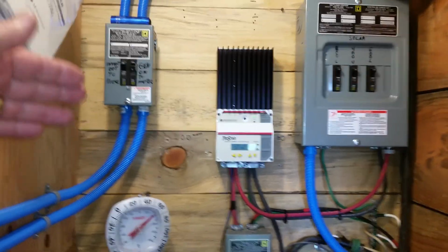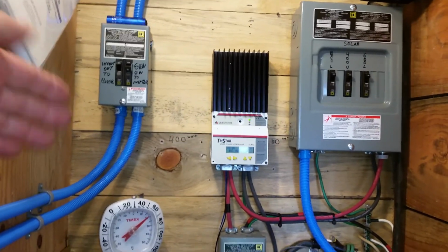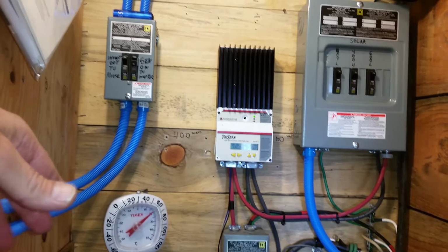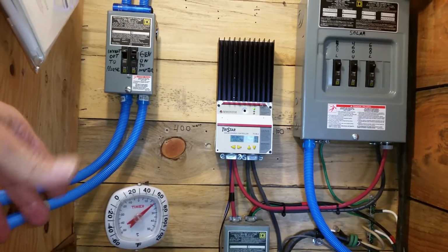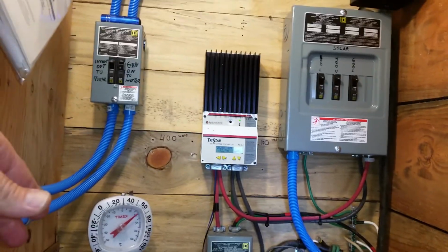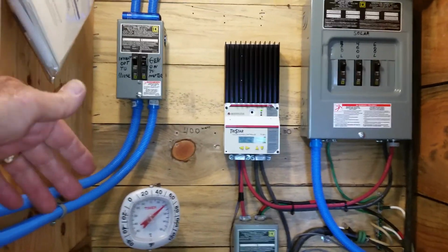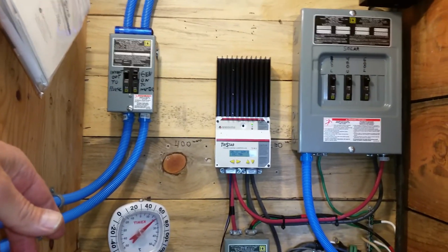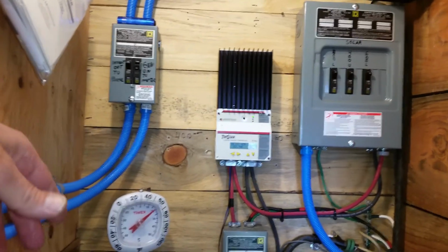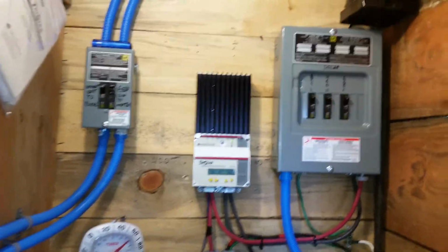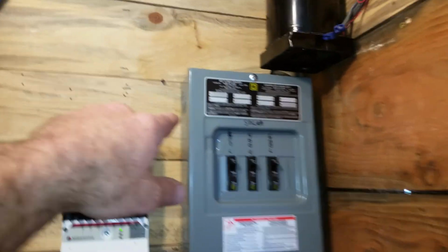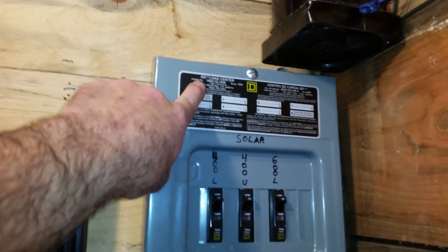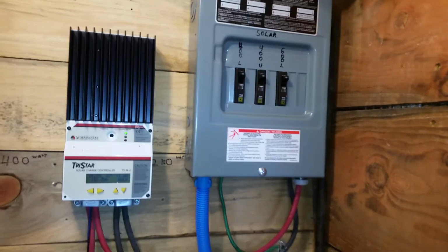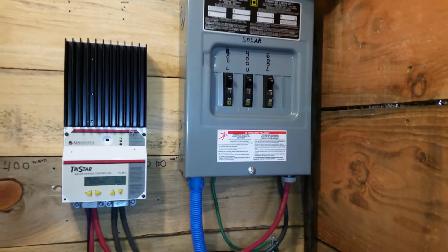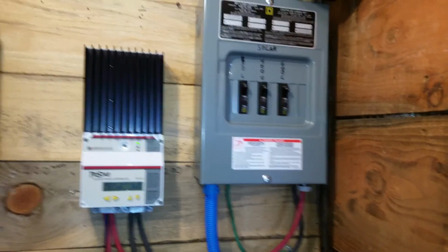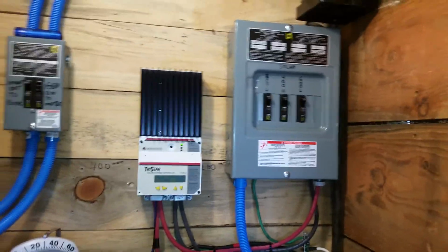So having the right charge controller, the right size wire, the right fusing, the right breakers, etc. I see so many systems that have AC household type breakers running with DC running through them, and they're just not rated for DC. As far as I know, Square D QO is the only one that's rated for DC, but if you're up to a 48 volt system, you've got to break both sides or put them in series.